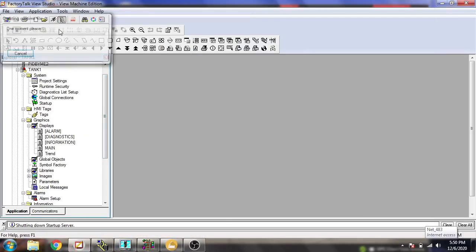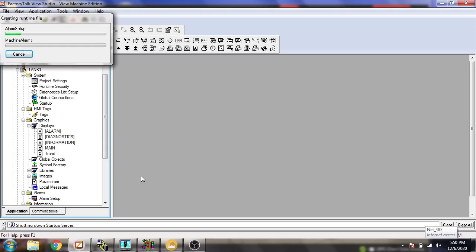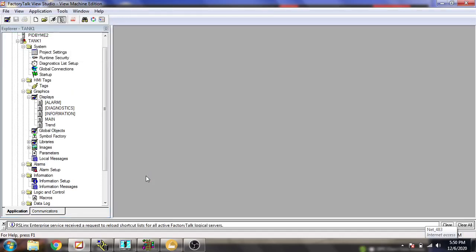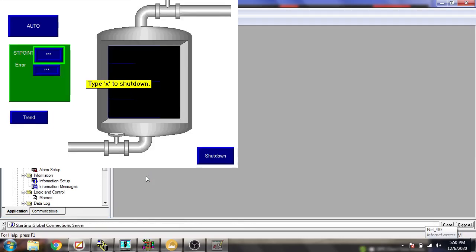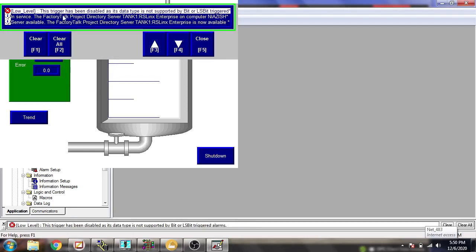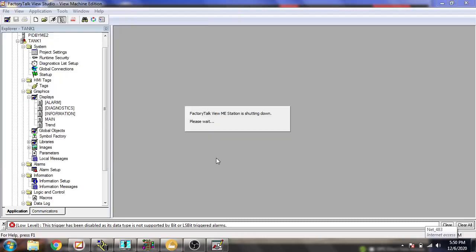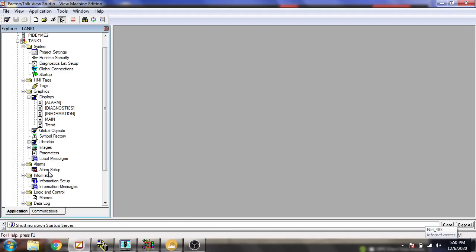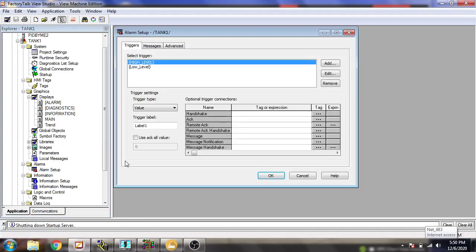Now I am just going to run my screen to check that the alarms are working or not. You will see the trigger has been disabled. It is recorded as a bit — I think we need to change it to value. So I am going to go back and select it as a value.